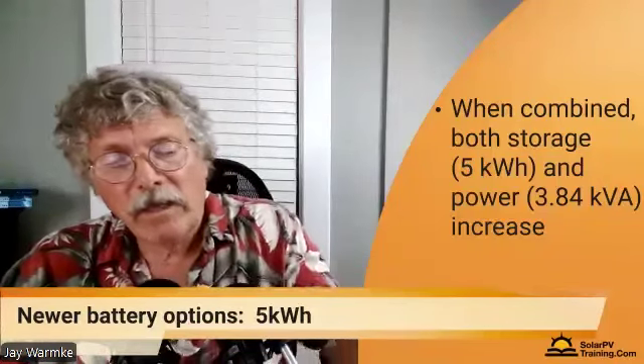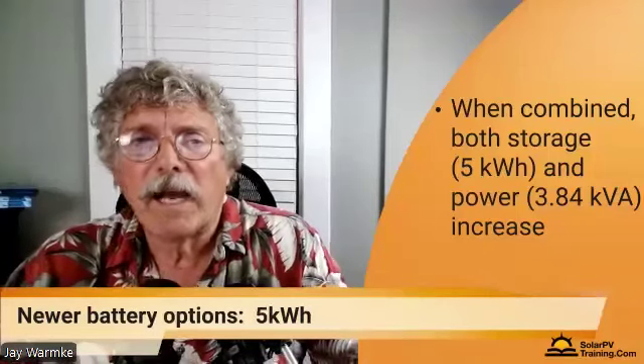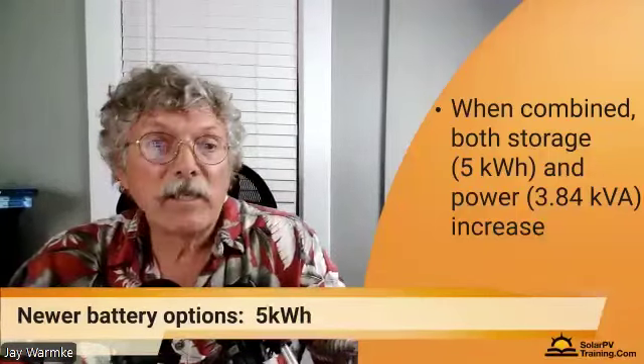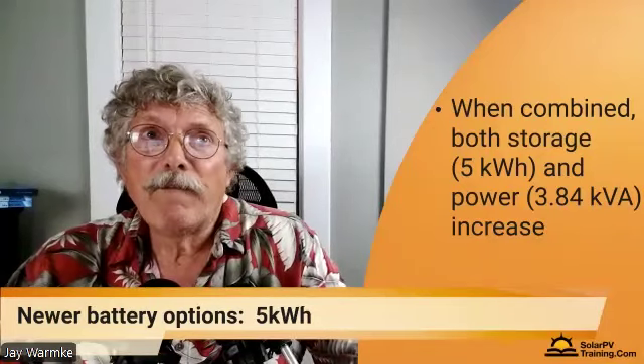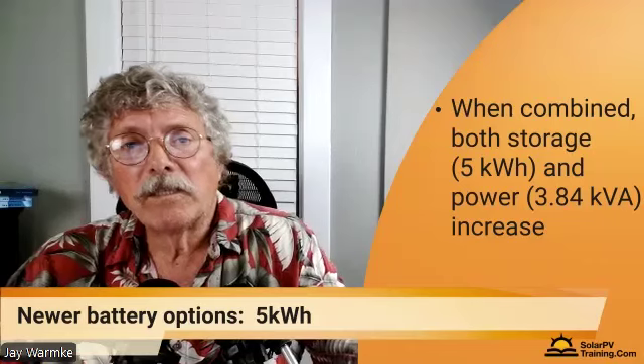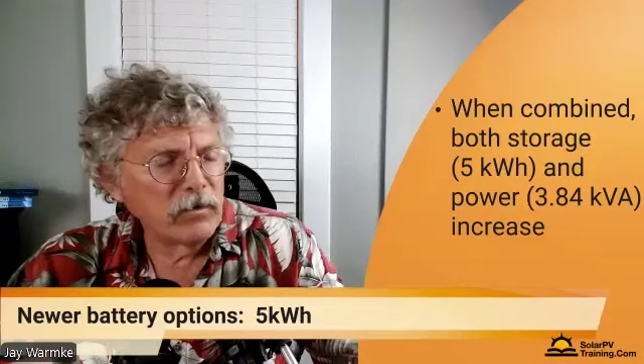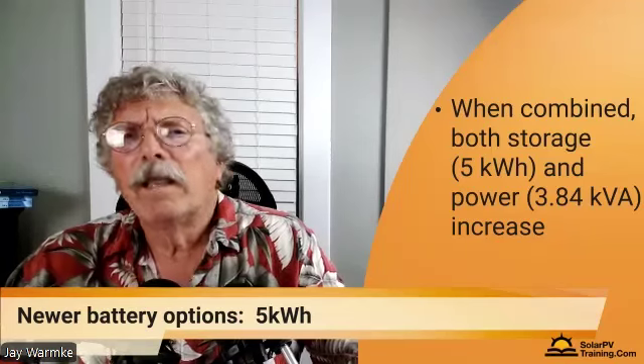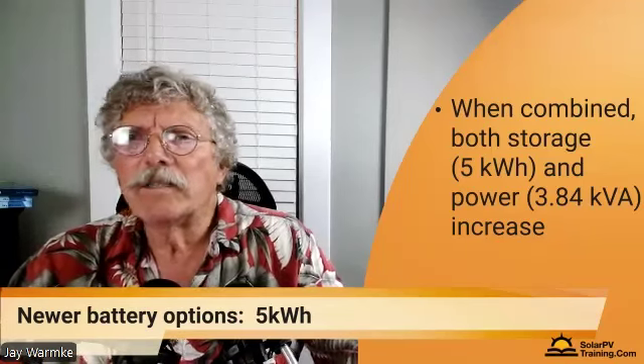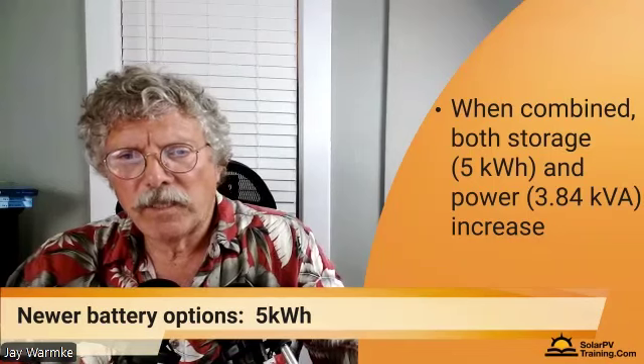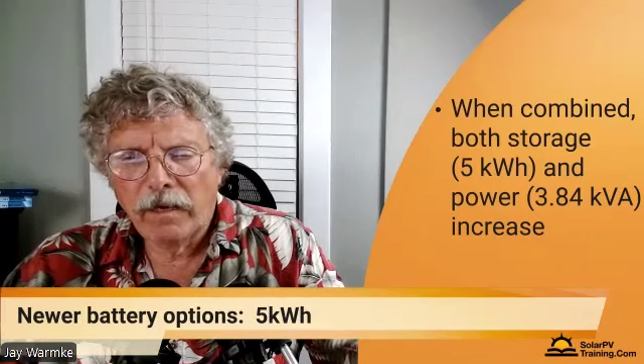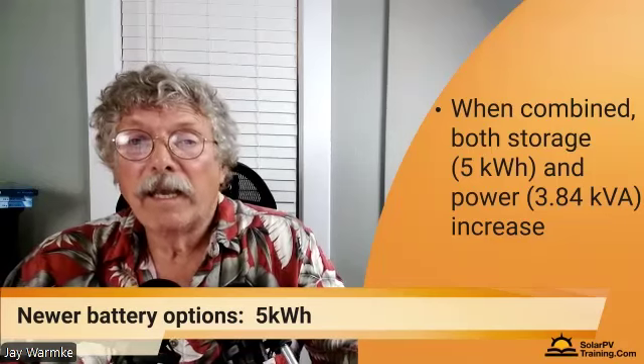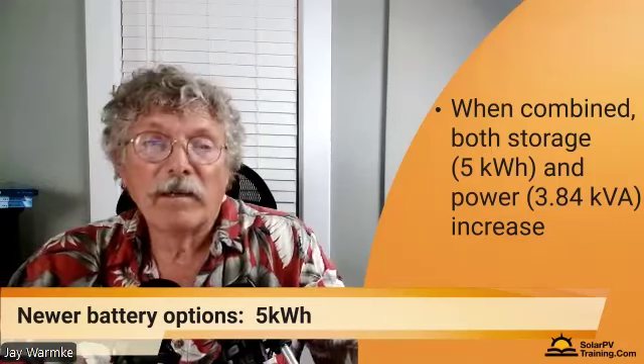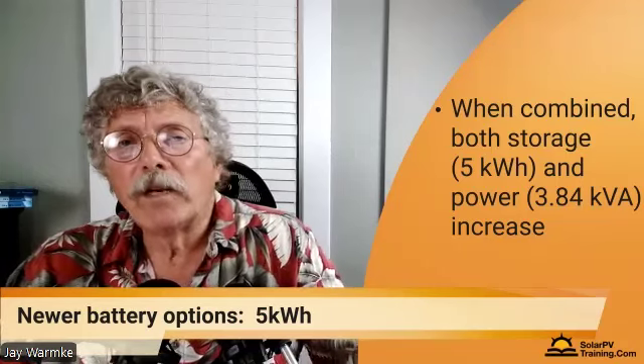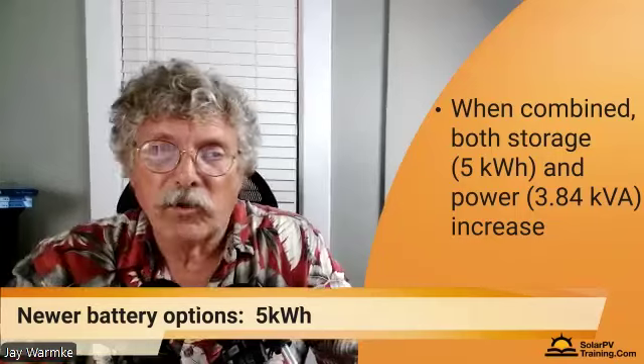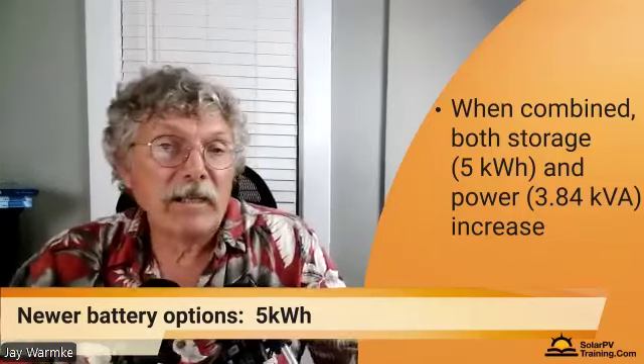Somebody in chat mentioned I'd said in a previous session that these batteries have to be stored outside, and yes, that's true. If you're in a jurisdiction subject to, I believe, the 2020 code - might be the 2023 - they're integrating new standards saying your storage system in a residential or occupied setting has a whole bunch of issues that fall into place. So most are saying it's got to be stored outside in a separate building, maybe not even in your attached garage.